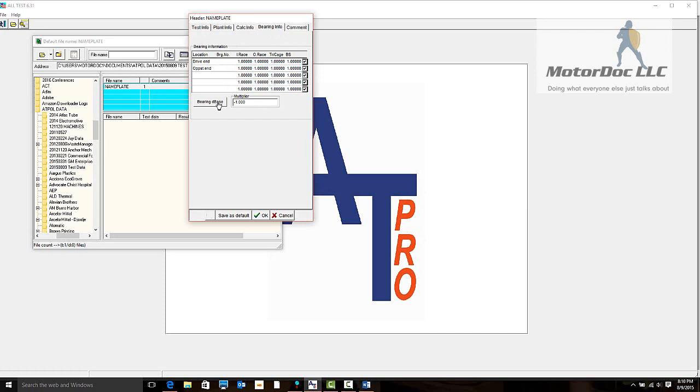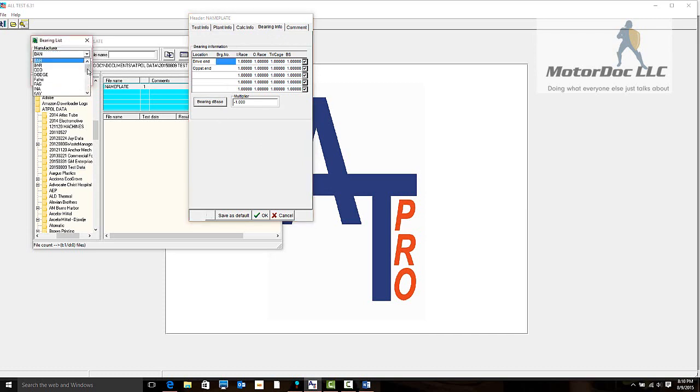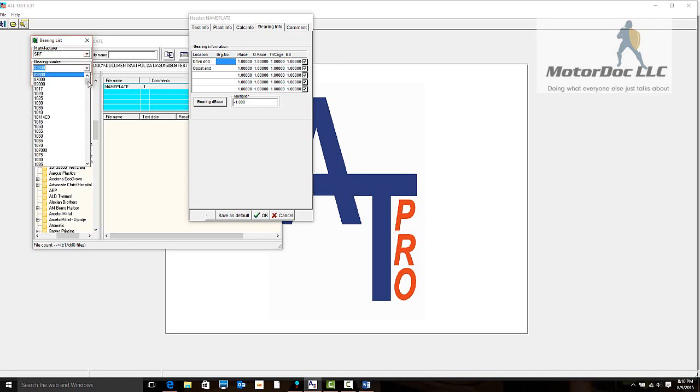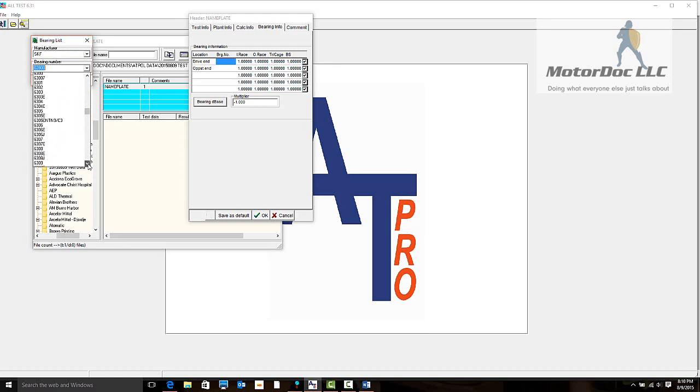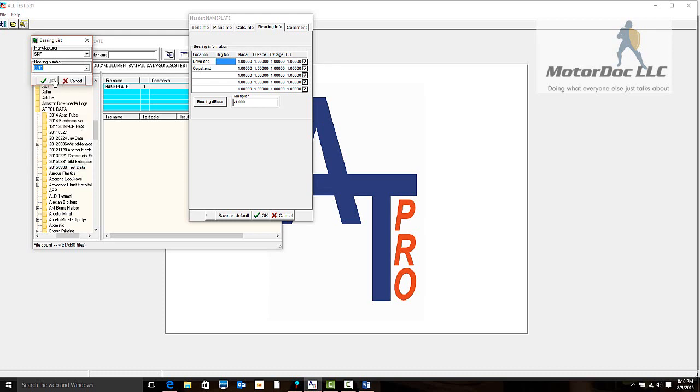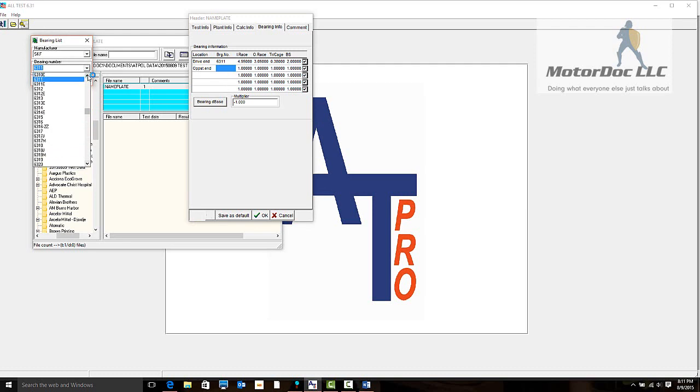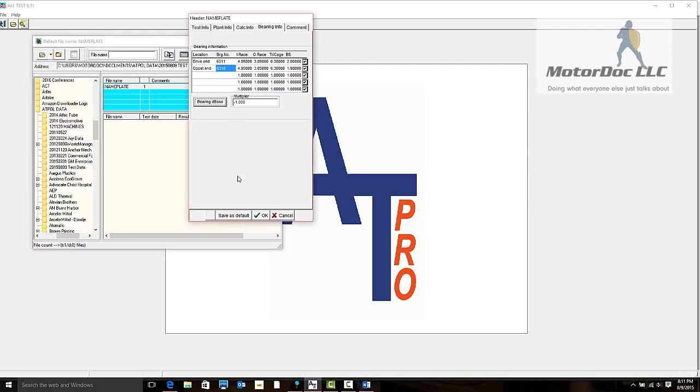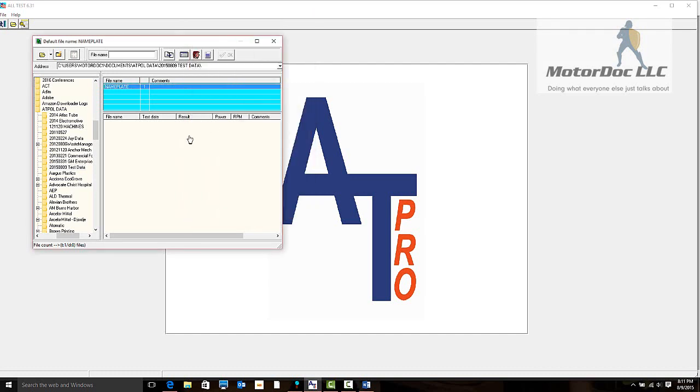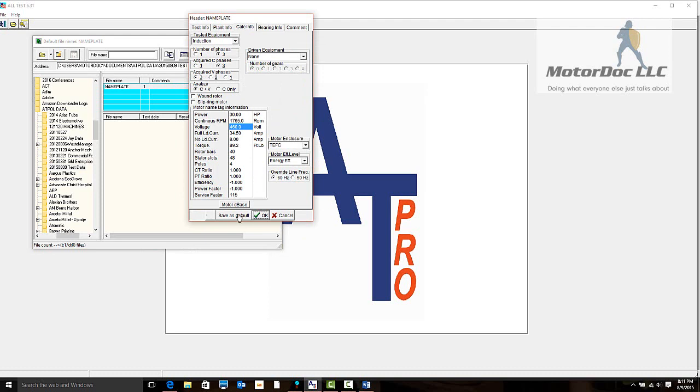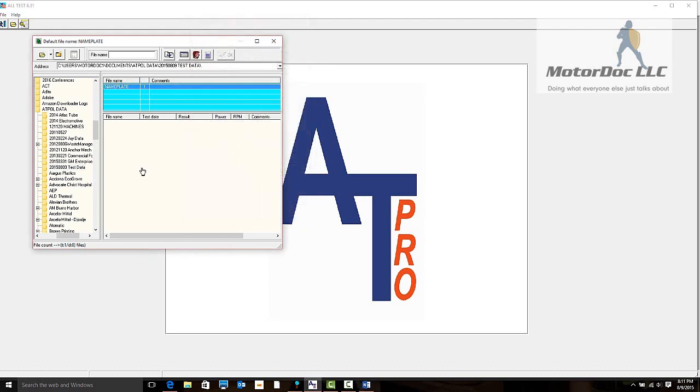Let's go ahead and find the bearing. We go into the bearing database. The drive end is an SKF 6311 and the opposite drive end is an SKF 6310. Let's find our SKF bearings. Here are the SKF bearings, and now we're going to scroll down to the 600 series. So 6311 for this one. Notice all the multipliers have come up, and this one will be a 6310. Now we have all of this information in our nameplate, which we then want to save as default. Now anything that comes into this will be set up for that.